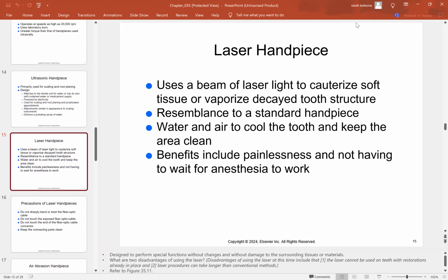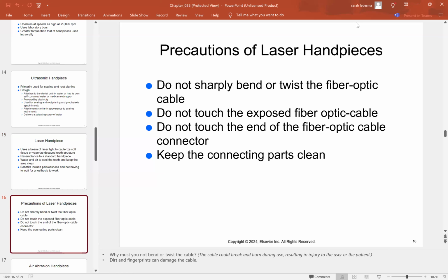The laser handpiece uses a beam of laser light to cauterize soft tissue or vaporize decayed tooth structure. It resembles a standard handpiece, with water and air to cool the tooth and keep the area clean. Benefits include that it's painless and there is no waiting for anesthesia to work. Precautions for the laser handpiece: do not sharply bend or twist the fiber optic cable. Do not touch the exposed fiber optic cable. Do not touch the end of the fiber optic cable's connector, and keep the connecting parts clean.